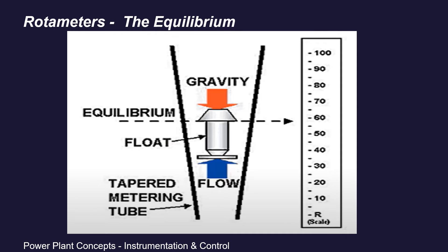The process reaches an equilibrium when the upward force — mainly the drag force — equals the weight of the float. This gives the float a fixed position with no movement. The height gained by the float as it moves is proportional to the rate at which the fluid is flowing. The height reading can be easily taken from the side scale marked on the tube, where the calibrated value of the flow rate corresponding to that float height is displayed.